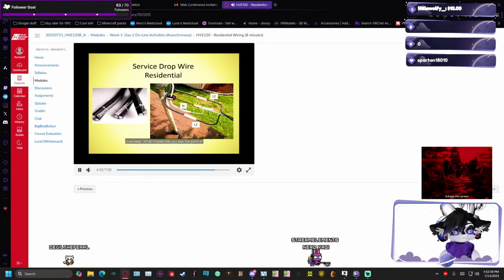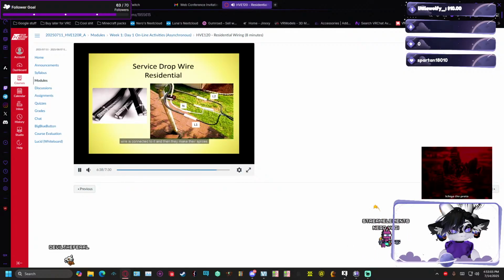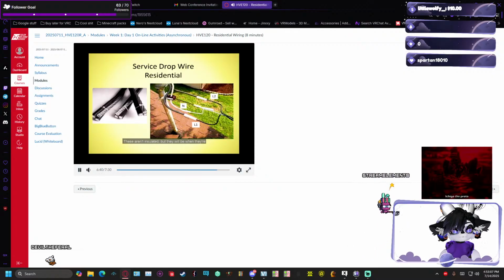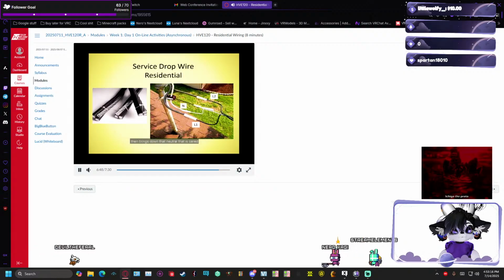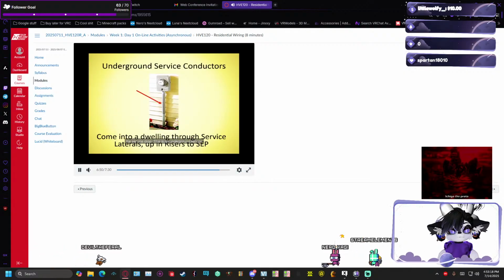Here's a better picture of it from overhead, what it looks like. You see the point of attachment where the messenger wire is connected to it, and then they make their splices. These aren't insulated, but they will be when they're completed. You see with the blocks on it, L1 and L2 are your 120 volt legs, and the neutral or messenger then brings down that neutral. That is called a service drop.